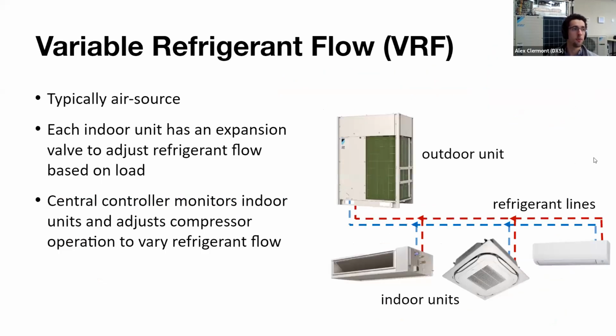Next, we'll get into another type of air source heat pump, probably the most common commercial air source heat pump that you will find. This is probably Mike's and my favorite topic, and we've talked about this for a long time, but what we're looking at here is that each indoor unit on the right has an expansion valve. It can adjust how much refrigerant it wants based on the load in the space.